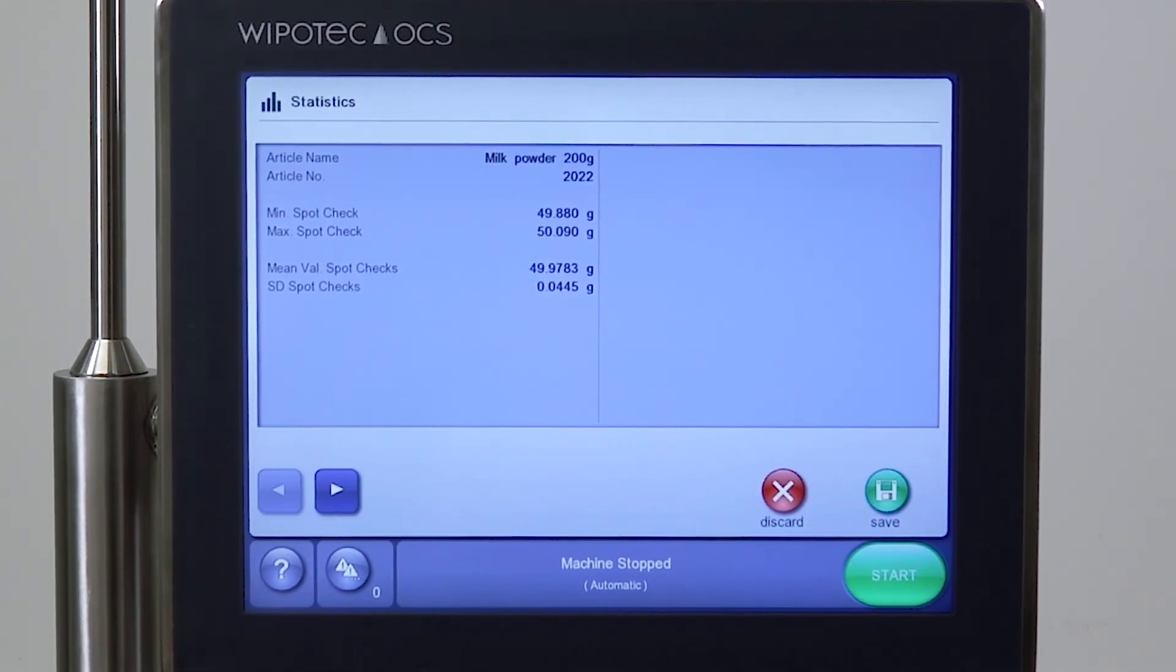We finish the spot check at that position. We can see that the precision of the checkweigher and its uncertainty is 44.5 milligrams and that the average weight reading after 30 readings is 49.9783 grams. From my point of view, this is a very precise dynamic checkweigher.